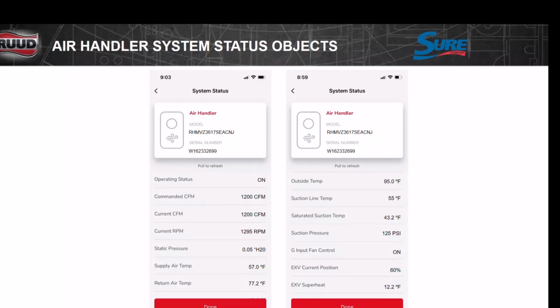It'll give you an alert? Yep. When you first turn the system on, if you have it on the EcoNet controller for sure, it's going to give you an alert code. It'll go away, and then it will continue to operate normally until it reaches the higher CFM as it saw before, and then it's going to throw it again. It may not throw it for a month, but if the filter starts getting stopped up, it's going to start throwing it. Blower cutback's going to go in, and you're going to have all kinds of problems.